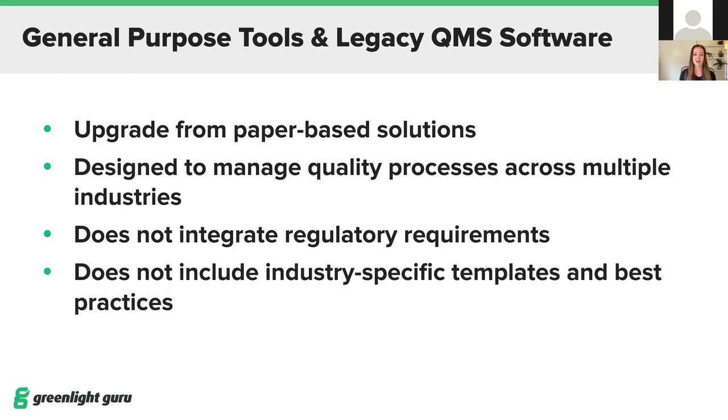So these, once again, are just some generally built programs for storing your documents, but maybe don't have the exact workflows that you need for things like change management, or what happens when a CAPA comes into place, what workflow do I need to follow for that appropriate root cause analysis, investigation, verification, all those different common workflows that you need to have as part of 13485, and also the risk management side as well, as far as identifying those hazards and harms and kind of the whole fun workflow.